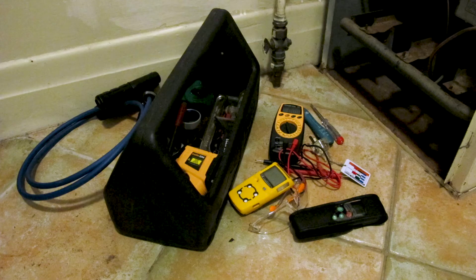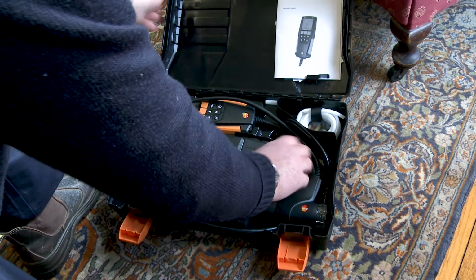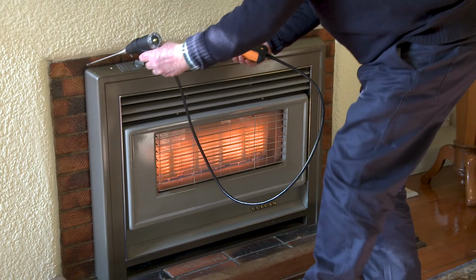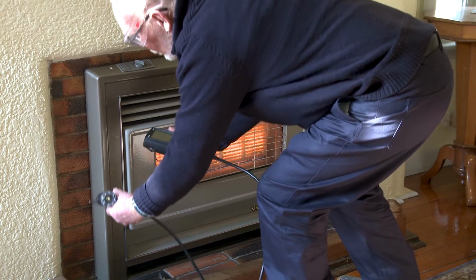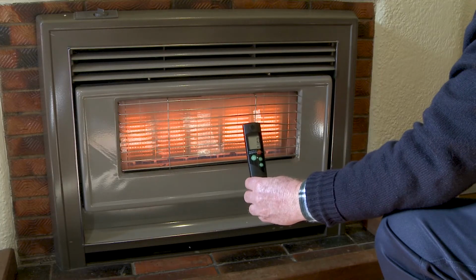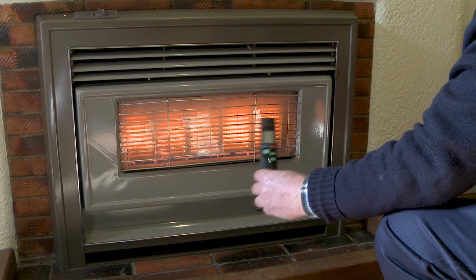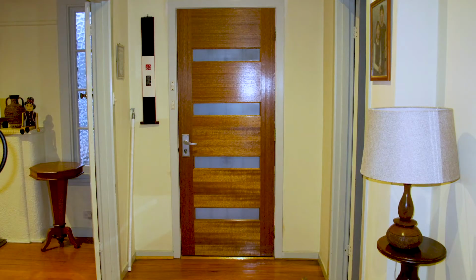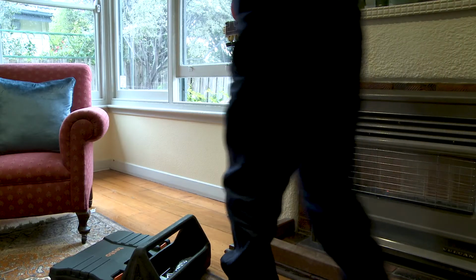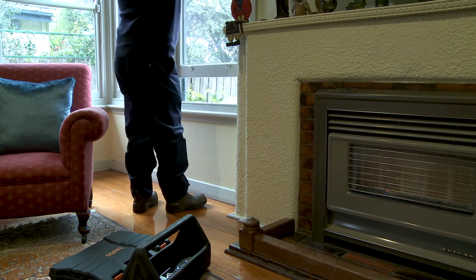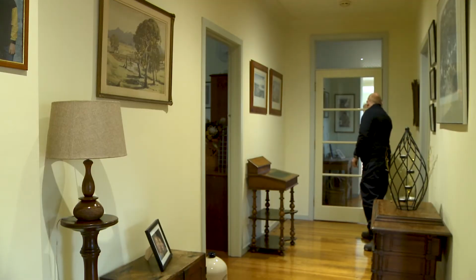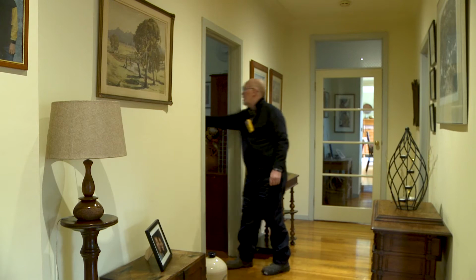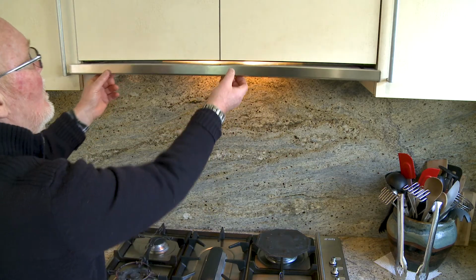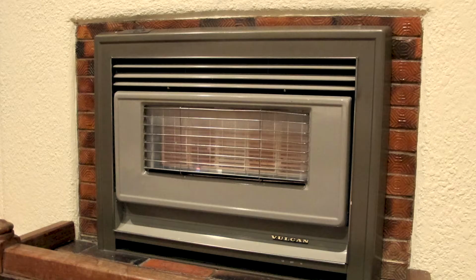Test 3. Spillage testing. It's important to use the proper CO testing equipment and make sure that it's calibrated yearly. The VBA and ESV recommend using probe-type CO testing equipment. Equipment without a sampling probe may be damaged and show a false reading if placed in the heat stream. Ensure all external doors are closed and any windows open during the negative pressure test are closed. Open or close any internal doors that connect the space between the gas appliance and any mechanical extraction fans, including range hoods, to create the greatest negative pressure effect on the appliance.